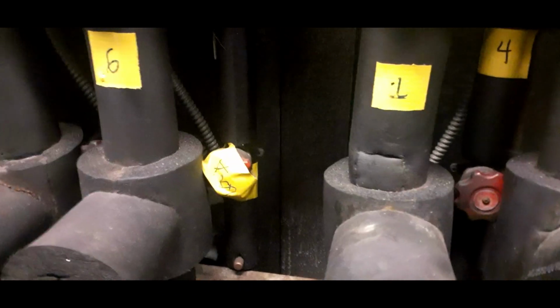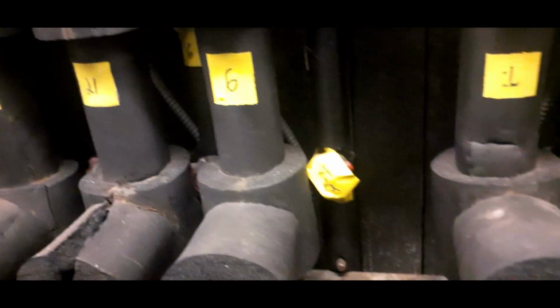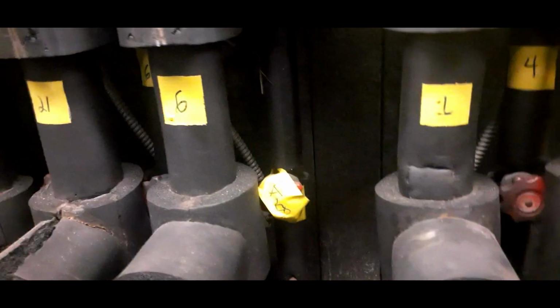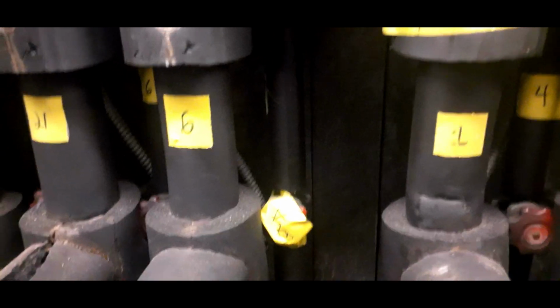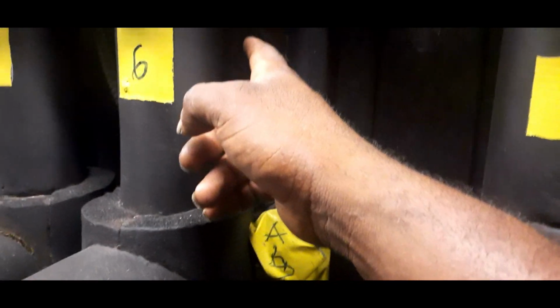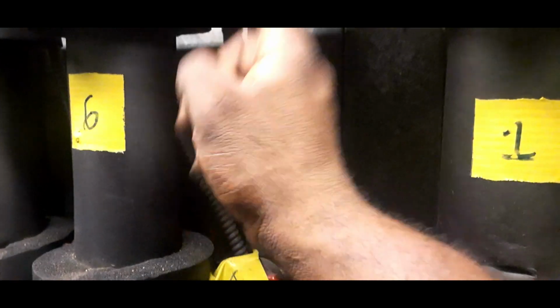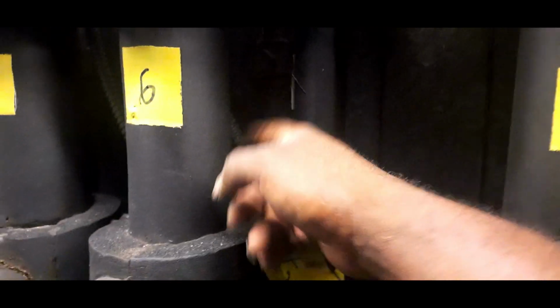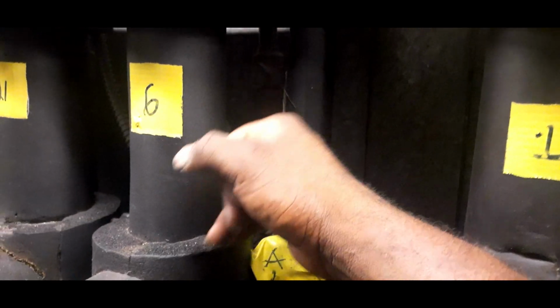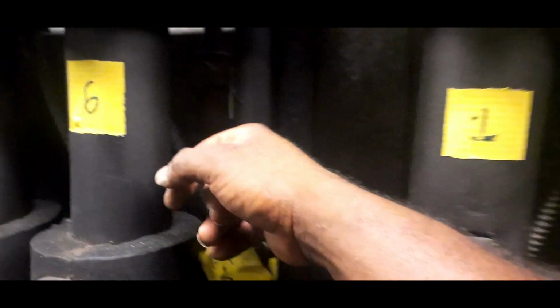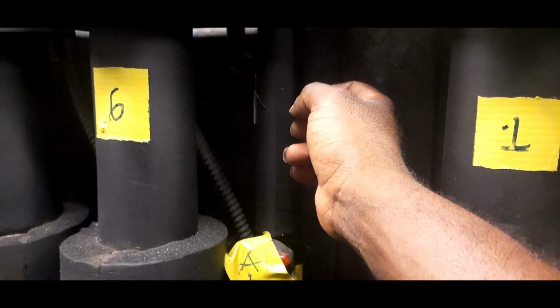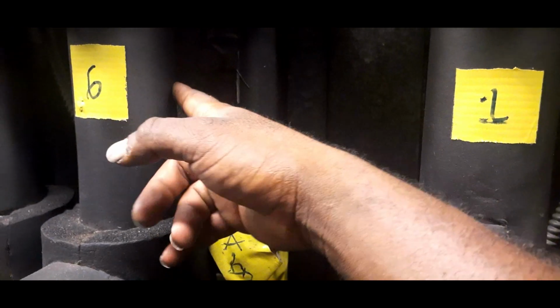Before I head downstairs, since this is an ice cream case and I can see the ceiling noise back there, that let me know that this rack here has hot gas defrost. So if I'm gonna go down there and open that screen, I want to make sure that it's not going to go on defrost while I'm checking the screen. Make sure that I close this ball valve before I go down there and open up the TXV screen, because this has hot gas defrost. If I open that screen up and it goes into defrost, I'll be in real trouble. We'd have hot gas refrigerant entering the sales floor. So the best thing to do is just valve this off and you don't have to worry about it. All right, so that's closed. Now I'm gonna go down there and check the screen.